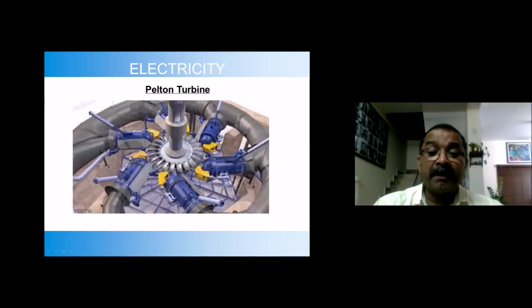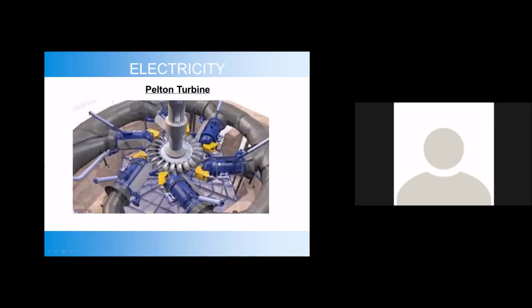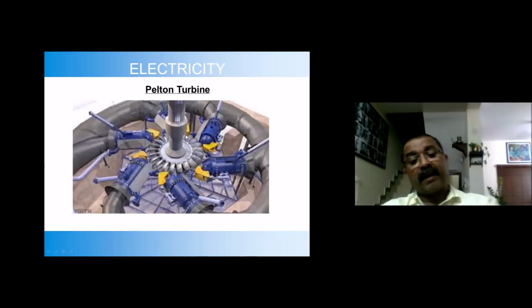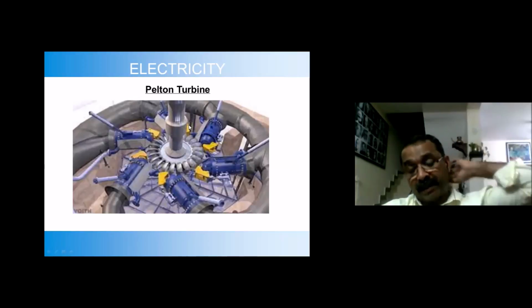Okay, here a big alternator is here. Actually, to this Pelton wheel, we are pumping from 6 water jets arranged here. Water will be coming this way, and it will hit the first jet, second jet, third jet, in such an arrangement. Actually, in our Idukki power station, this is exactly the arrangement.